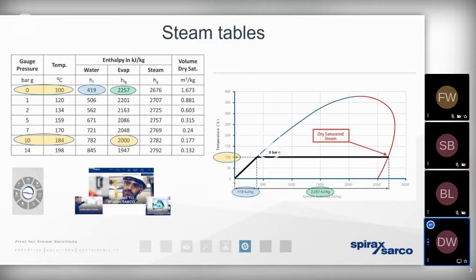We know that water's got a specific heat capacity of 4.19. In other words, if we want to add 1 degree of temperature to a kilogram of water, we need to add 4.19 kilojoules of energy to it. So in other words, at 0 bar gauge, we know that water boils at 100 degrees. Therefore, we need to add 419 kilojoules of energy to that water to bring it up to boiling point. We can refer to that as the enthalpy of water. We can also refer to it as the sensible heat.